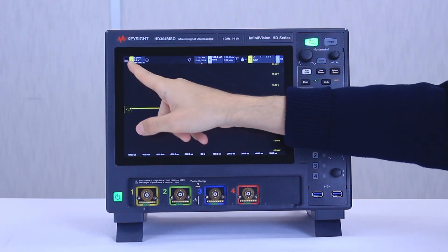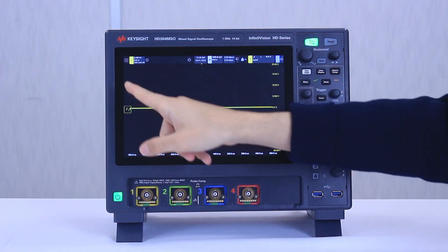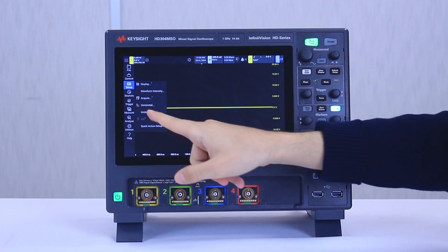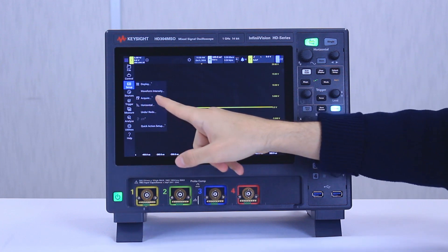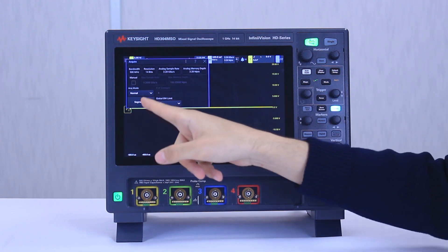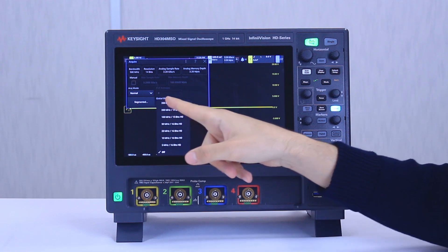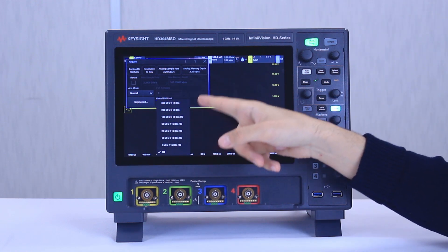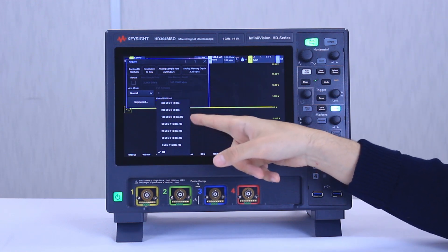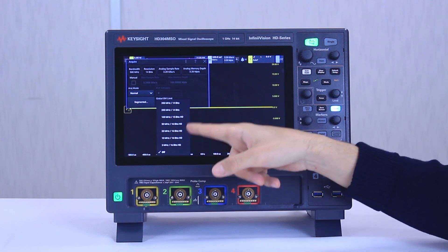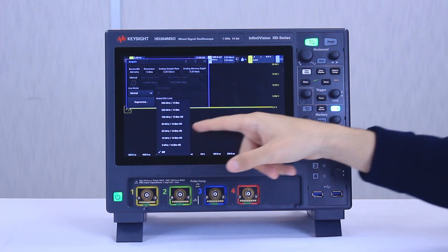If we go to the main menu, go to setup, and click on acquire, we can have lots of different options for bandwidth filters. Previously there was only a 20 MHz filter, but now we have more than one option in here.